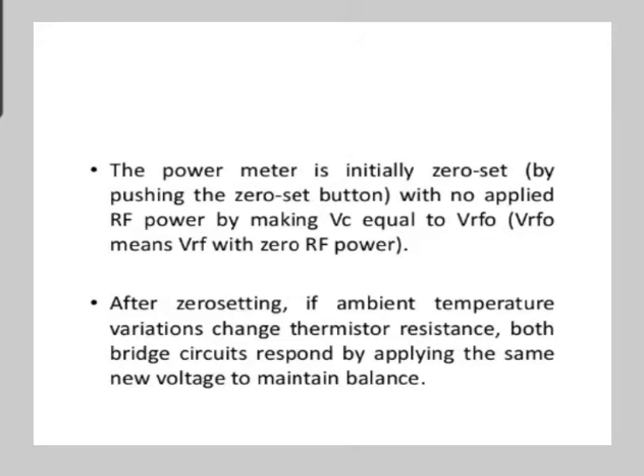The power meter is initially zero set by pushing the zero set button, with no applied RF power, by making Vc equal to VRF0, meaning VRF with zero RF power. After zero setting, if ambient temperature variations change the thermistor resistance, both bridge circuits respond by applying the same new voltage to maintain the balance.